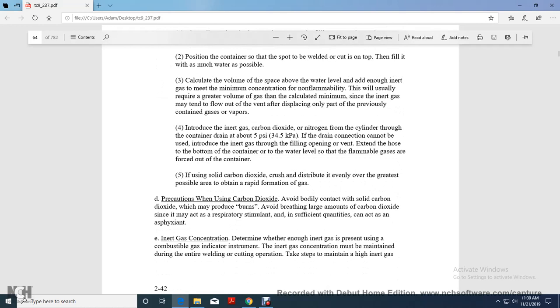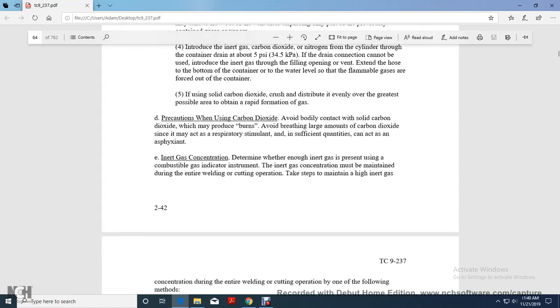Introduce inert gas, carbon dioxide or nitrogen, from the cylinder through the container drain at about 5 psi. If the drain connection cannot be used, introduce the inert gas through the filling opening by extending the hose to the bottom of the container. The water level will force the flammable gas out of the container. If using solid carbon dioxide, crush it and distribute it evenly over the greatest possible area to obtain rapid formation of the gas. Precautions when using carbon dioxide: avoid bodily contact with the solid carbon dioxide, which can produce burns, and avoid breathing large amounts of carbon dioxide, since it may act as a respiratory stimulant and in sufficient quantities can cause asphyxiation.